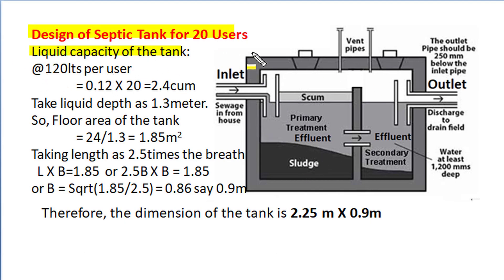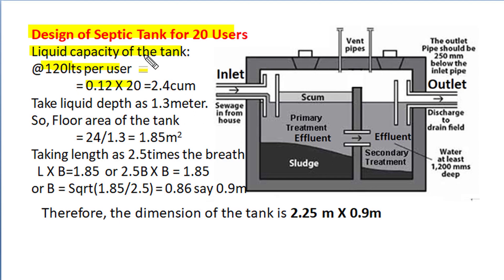Let's make a typical design of septic tank for 20 users. We can find out the liquid capacity of the septic tank by considering 120 litres of liquid waste per user. For 20 users, the per-day liquid waste capacity will become 2400 litres. Since 1000 litres corresponds to 1 cubic metre, the volume of liquid handled by the septic tank is 2.4 cubic metres.